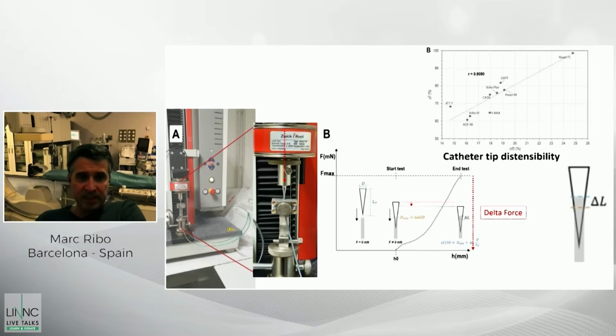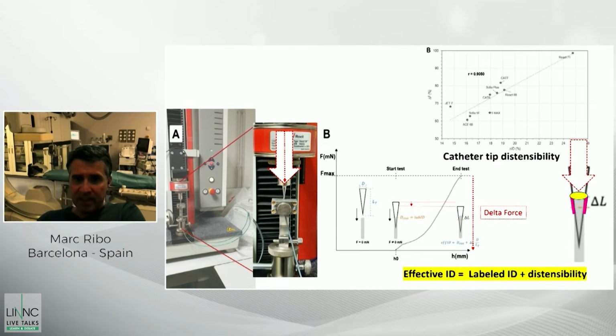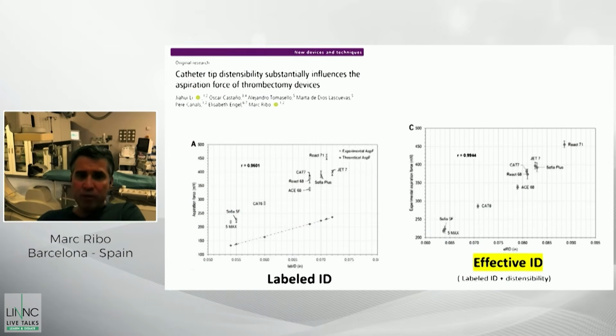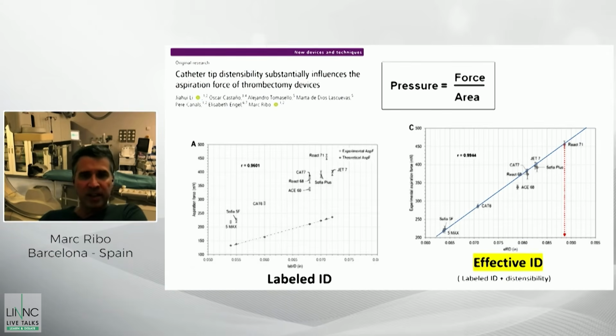Why is this? We tried to explain this, and to do that, we now put the clot analog, but instead of aspirating, we just applied the pressure that we observed, the delta pressure for each catheter, in the other direction. So we measured the distensibility of the catheter tip. So now we had the effective inner diameter instead of the labeled inner diameter. And if you apply the formula with the effective inner diameter, you can see that all catheters are in the same line. So in fact, what drives the detachment force is the effective ID. So those catheters with more distensibility would have much higher effective IDs and better optimized forces to withdraw the clot.